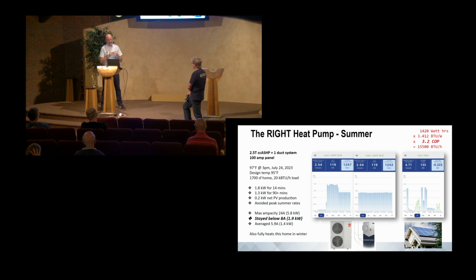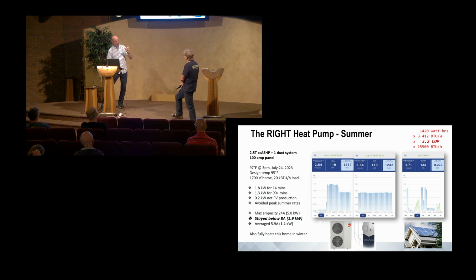But if it doesn't see enough gain over 24 minutes—and that 24 minutes is adjustable, you can dial it back to 14 or push it out to 29—then if it hasn't done what you're asking within that time frame, it'll kick on the backup heat just a little bit for as long as needed, then cut off as soon as it reaches that point, and maintain the heat pump.